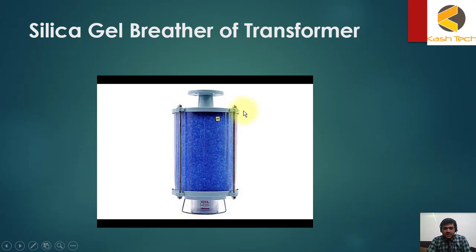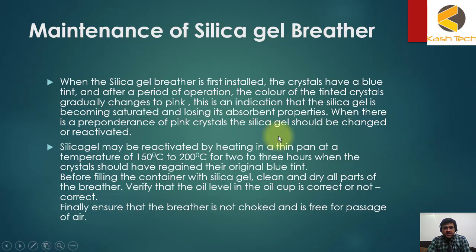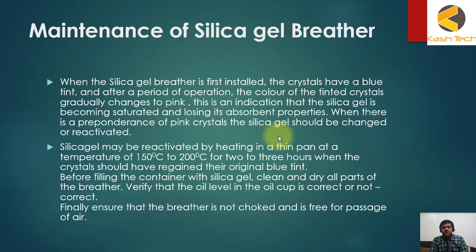Regarding maintenance of the silica gel breather: when it is first installed, the crystals have a blue tint. After a period of operation, the color gradually changes to pink, which indicates that the silica gel is becoming saturated and losing its absorbent properties. When there is a predominance of pink crystals, the silica gel should be changed or reactivated.